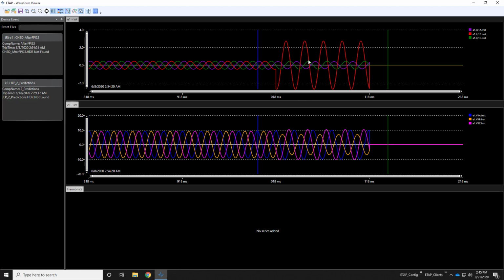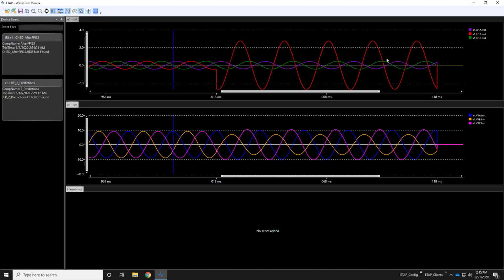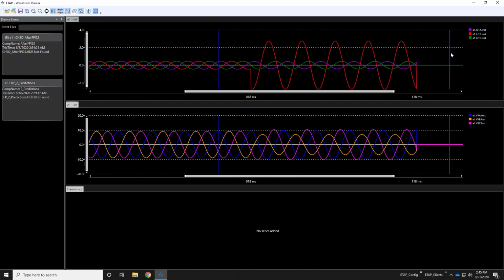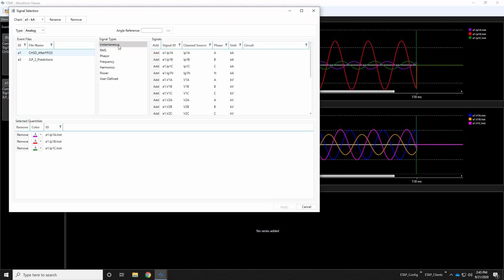As with any tool for waveform analysis, the standard panning and zooming capabilities are there. We have a time bar, which allows us to calculate the time difference between various events. So here's when the event happened, and you can see that's about 100 milliseconds of recording time for that event. Additionally, we can bring in new measurements. So here we have all of our instantaneous measurements. These are all the instantaneous measurements calculated, as well as RMS values.